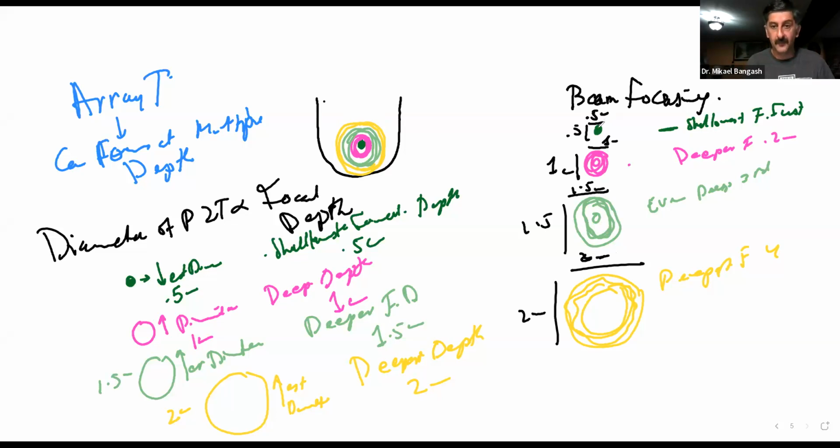First, the green one, the smallest one, is stimulated, followed by this being stimulated, followed by this, followed by this. So that phase-wise stimulation is why we call it phased. Array just means multiple focusing. The focal depths here are determined by the diameter of the PZT.